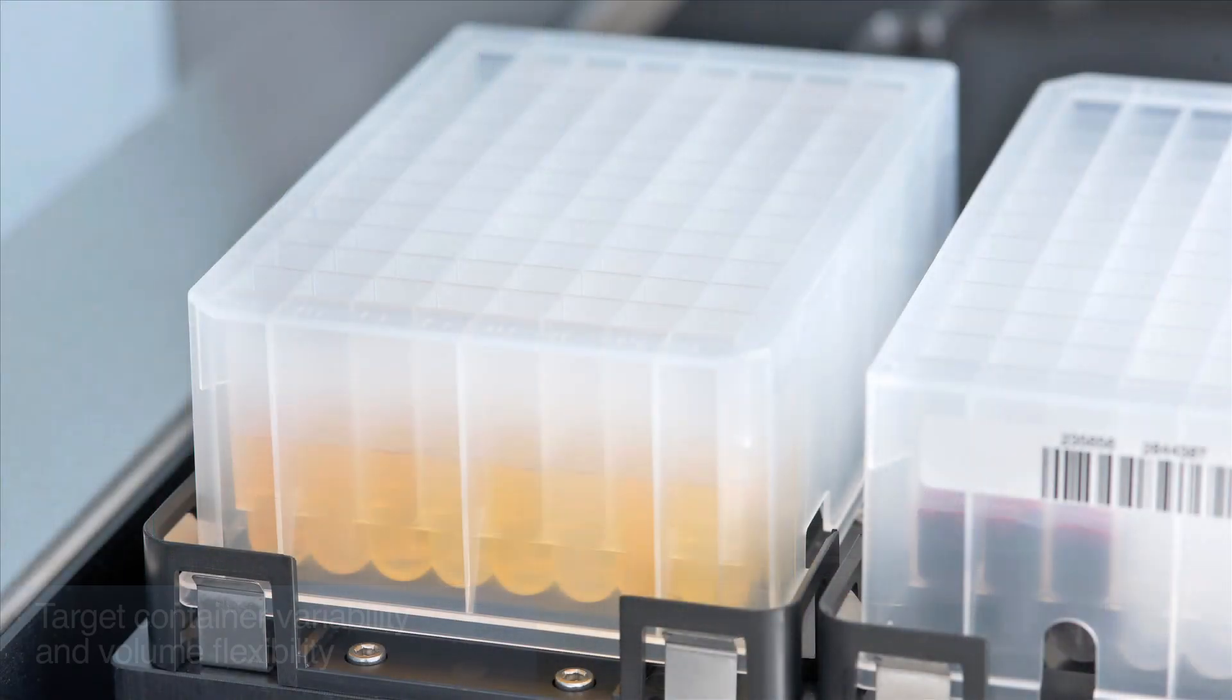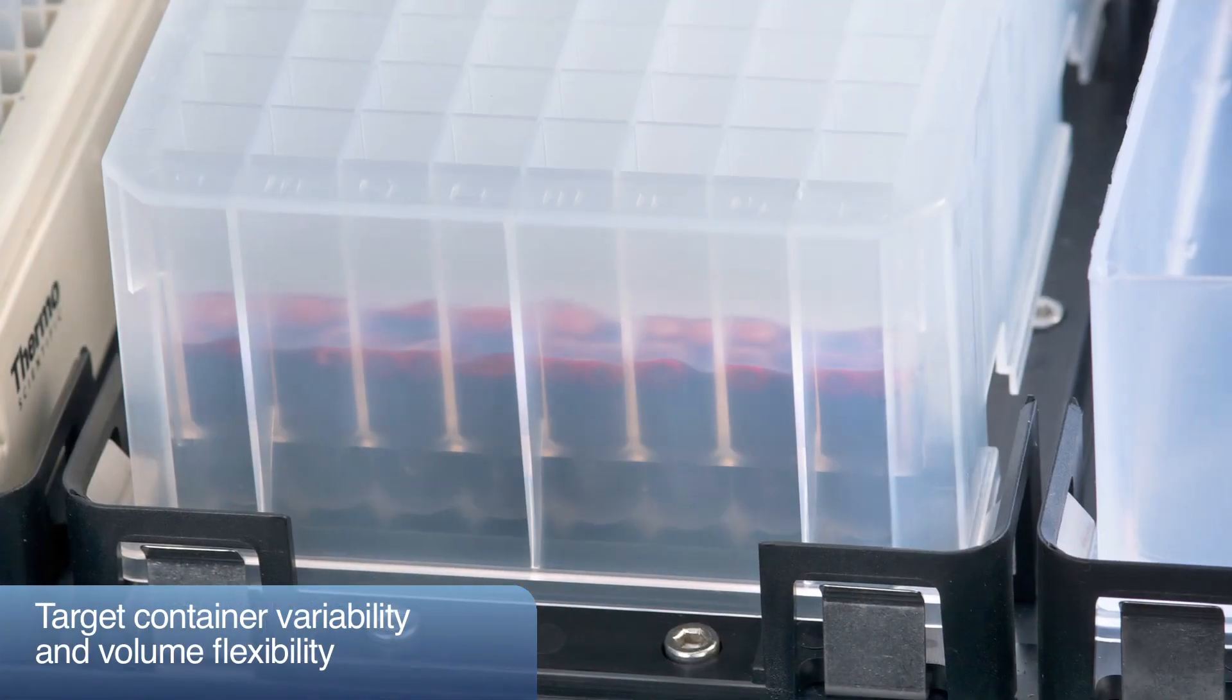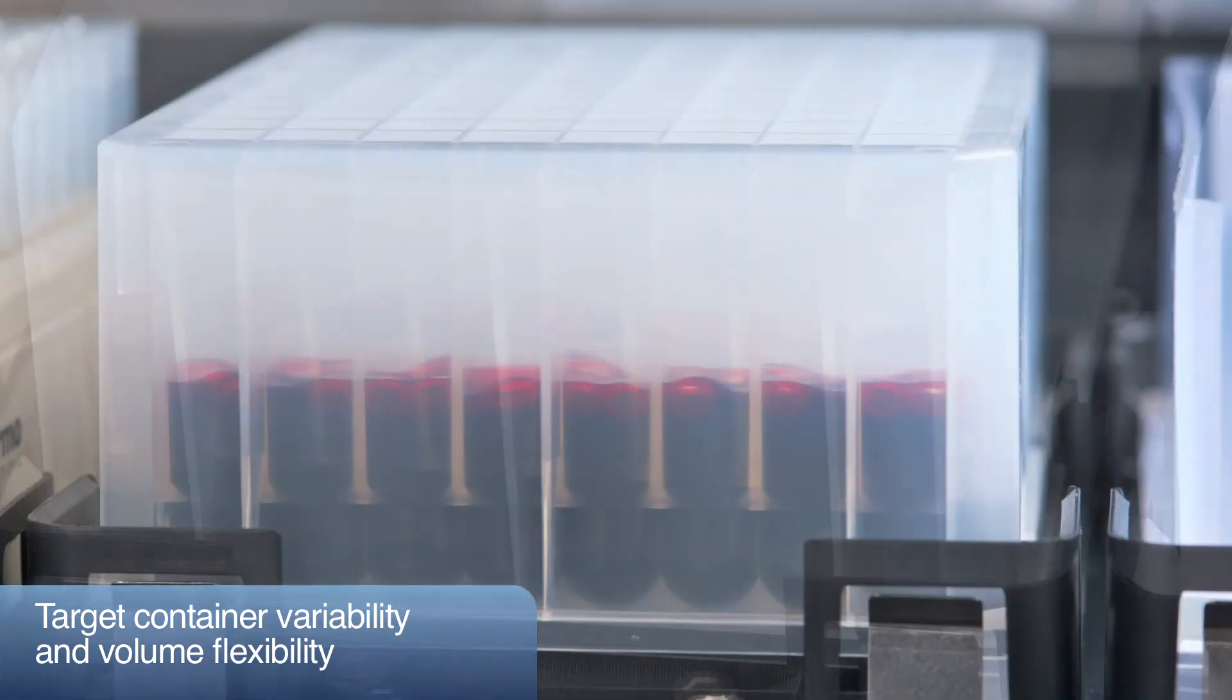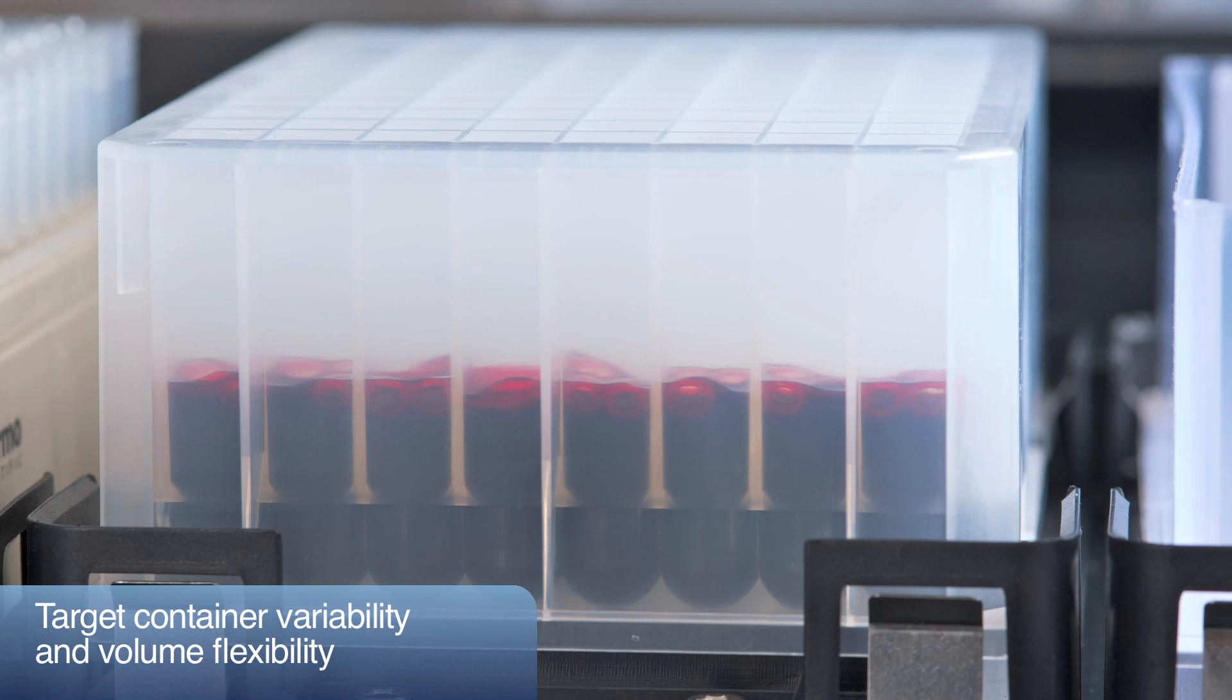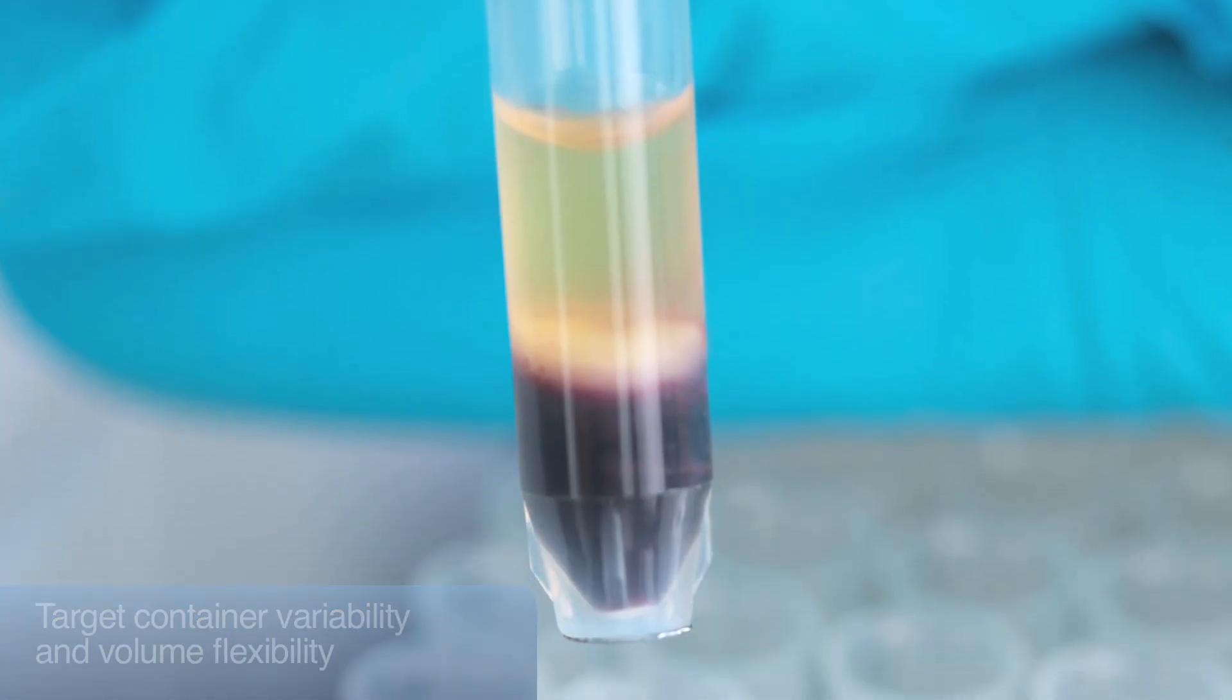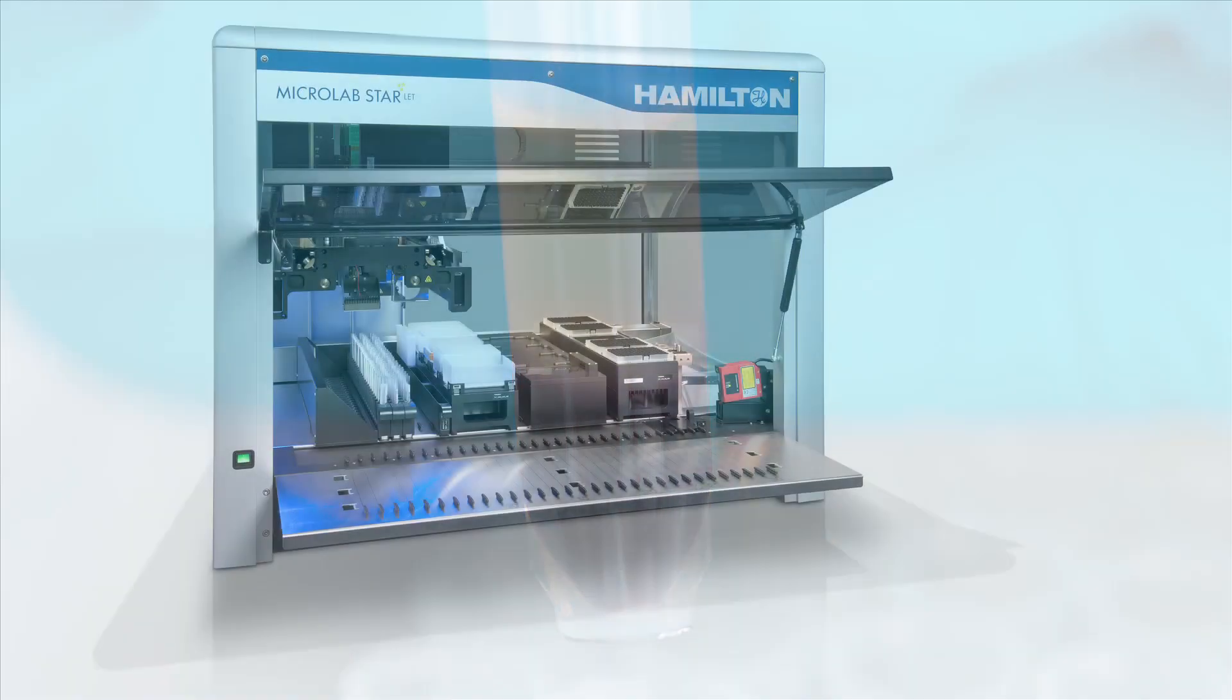After pipetting, the software provides a data file containing primary, intermediate and target container barcodes, pipetted volumes and sample status information, which can be sent to an LIS for sample traceability.